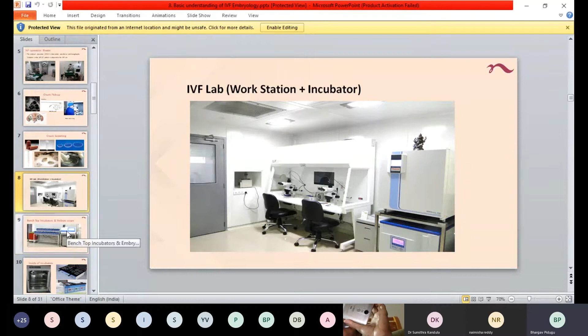So, benchtop incubator and embryoscope. A benchtop incubator is a compact incubator. The main advantage of this incubator is that the recovery is higher. When you open the incubator and check for the embryo grading, and when you close it back, the recovery of gas and temperature, everything, is quick. So the fluctuation in the temperature is minimal.